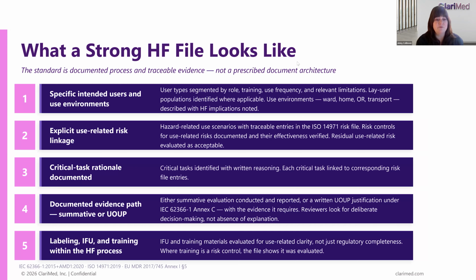I mentioned before that it's really important to document the reasoning for the selection of critical tasks or hazard-related use scenarios, because the reviewers really need to know why you've considered some things important and why some things aren't.